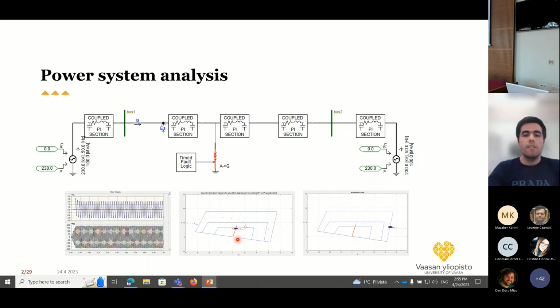So in this situation, since we have a precise equation for a power system, there is no need to use artificial intelligence or machine learning techniques. But what if we have a fault with high impedance, with different impedance ranging from, for example, 1 ohm, 2 ohm, 100 ohm, and even in the range of kilo ohm? In this situation, the problem will arise, and maybe there is a fault in the first zone, but because of that high impedance, maybe the relay sees it in the second or third zone, and maybe the relay is unable to detect such a fault.